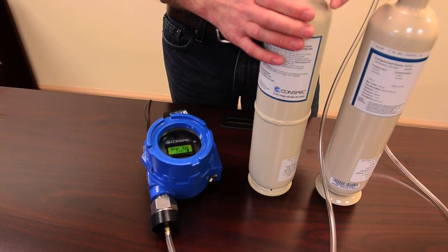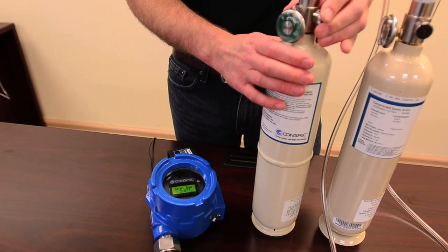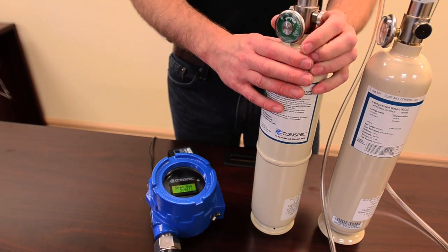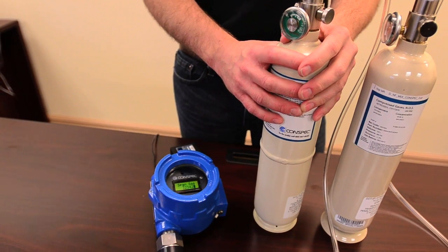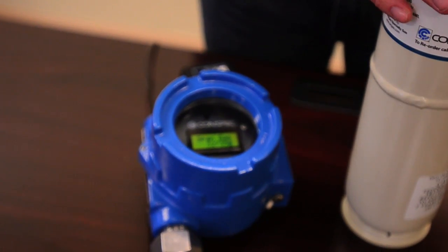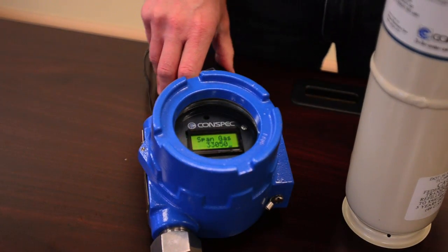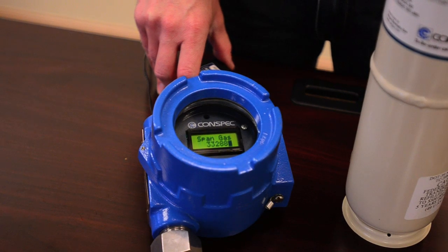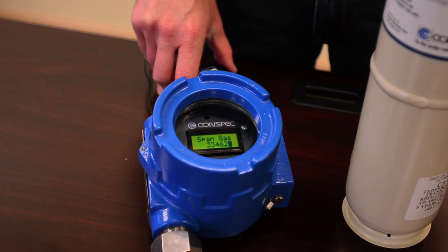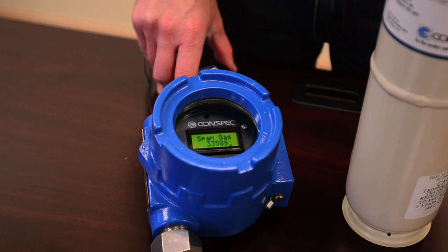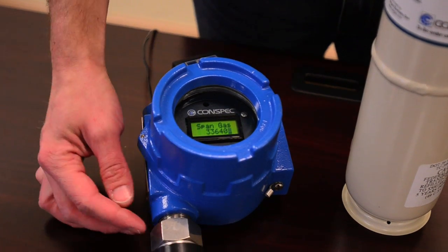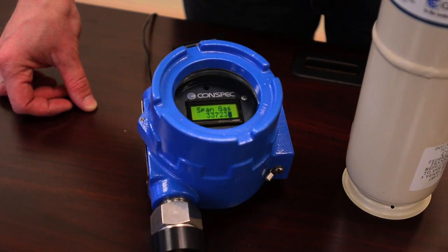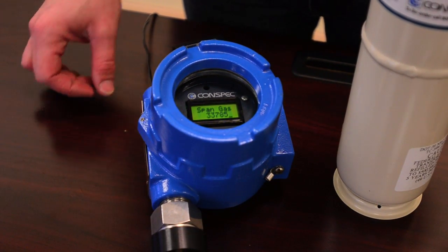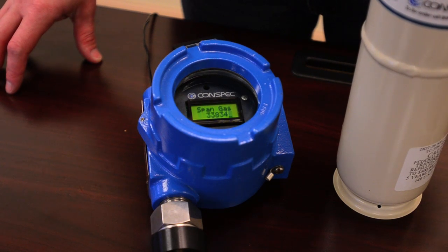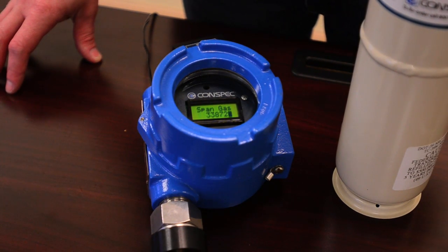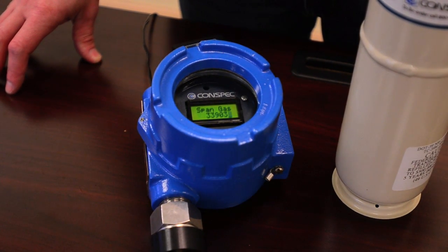We can turn on our cylinder. At this point we should start to see the value rise. It's a good idea to write down your values both for your zero and your span so that you have a reference when you're doing your calibrations and you'll know what to expect. Over time, as this sensor depletes, the output diminishes, so your values are going to shift a little bit, and it'll be a good indicator that your sensor's working towards failing.